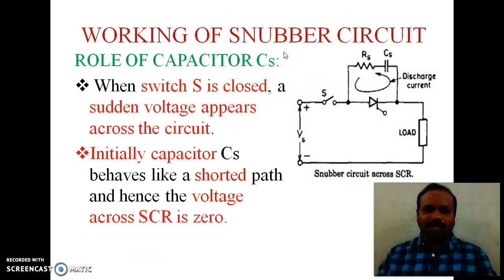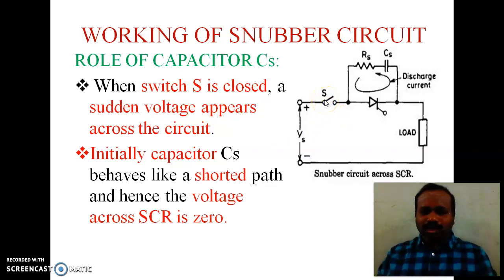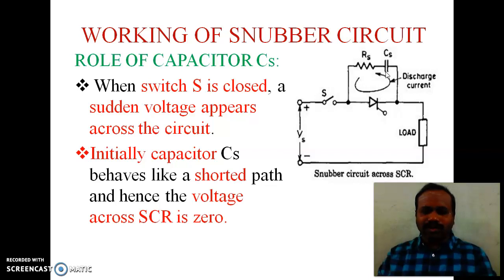Working of the snubber circuit: we first consider the role of the series capacitance CS. When switch S is closed, a sudden voltage appears across the circuit. If we close the switch S, the supply voltage suddenly appears across the thyristor, which is also present across the capacitor. Initially, the capacitor will act as a short circuit, so the voltage across the short circuit is 0. The same voltage is also present across the thyristor — that is, 0 voltage is present across the thyristor.